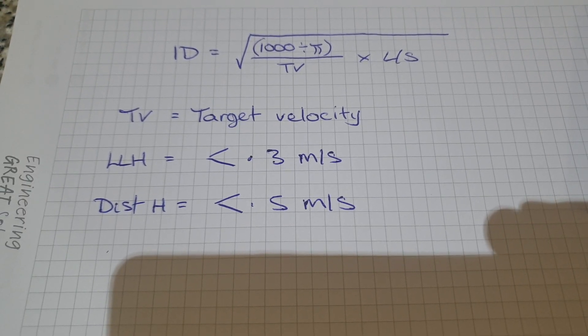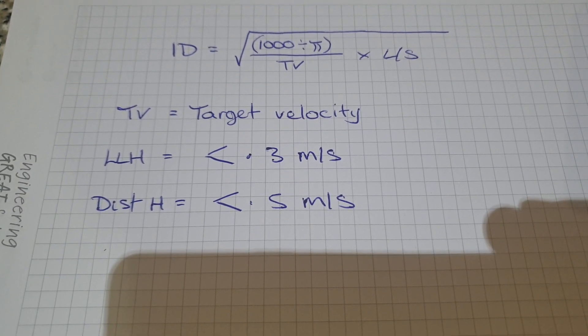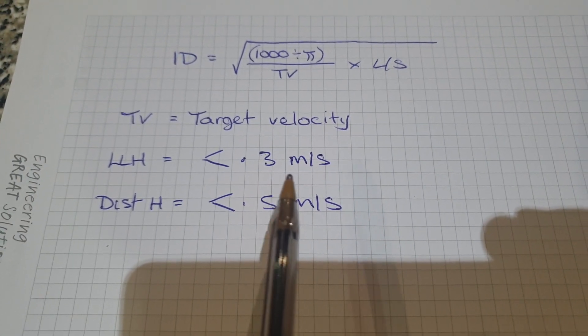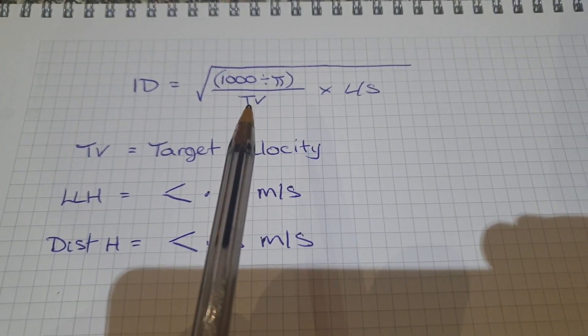So if you want to design a low-loss header, for example a tubed header, you know what your target velocity is. That's 0.3 meters per second. You can put the figures into this formula.